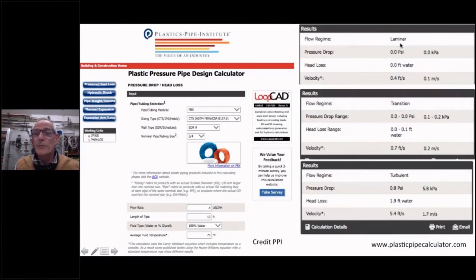So to get down to laminar flow condition, I had to get down to 0.4 tenths, under a half a gallon a minute flow rate, to get down to a laminar flow condition in a 3/4 PEX. And at that flow rate, we're looking at 0.4 feet per second. Think of water going through a pipe, how many feet per second, a half a foot per second, barely going to see that moving at that kind of flow rate.